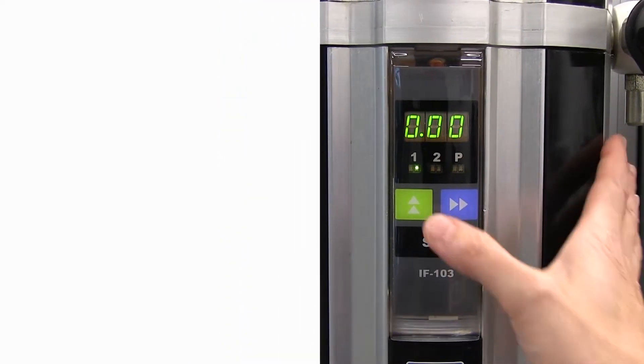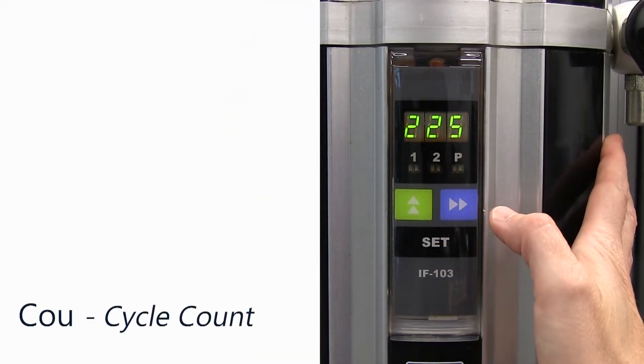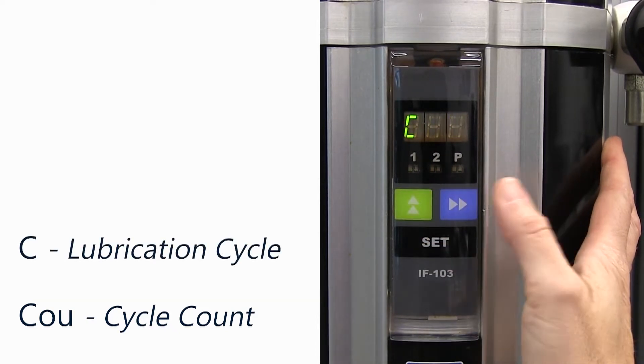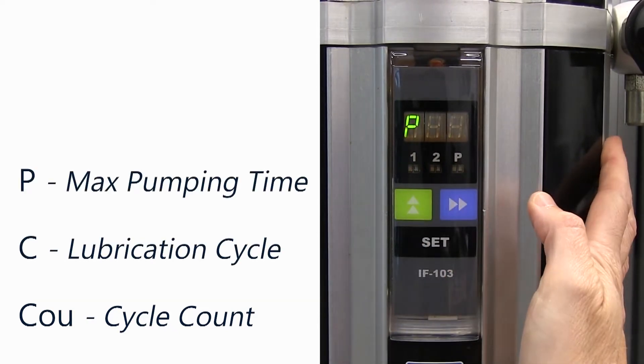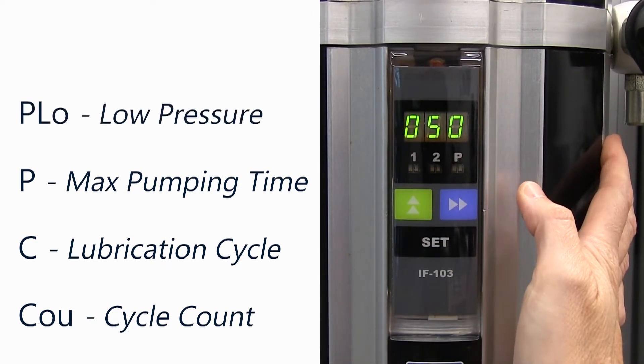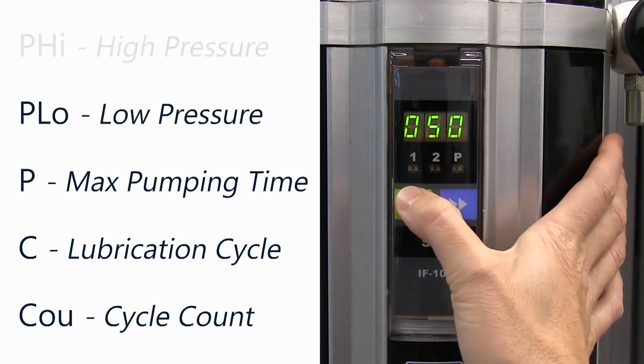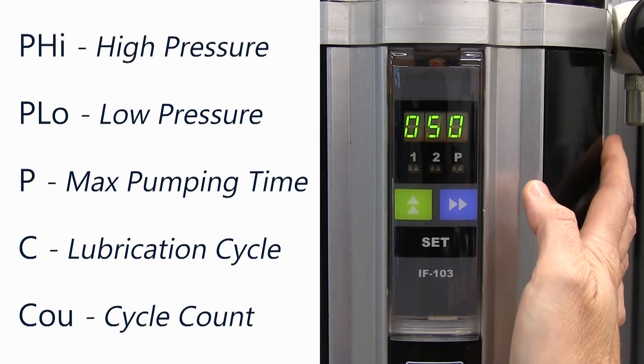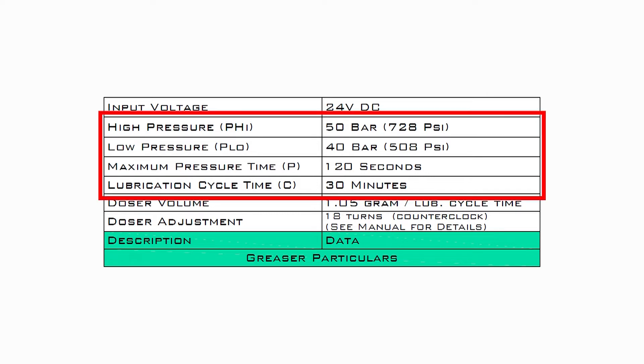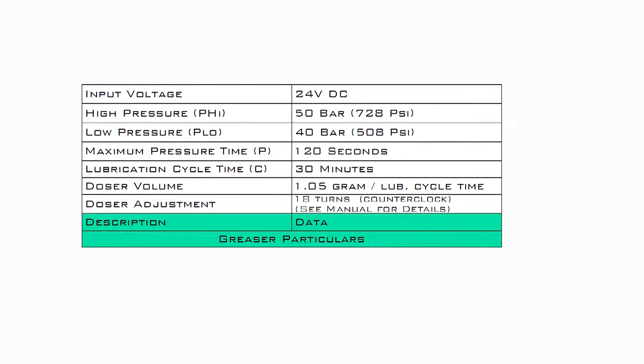Next, press the green up button to navigate through the standard parameters: lubrication cycle (C), maximum pumping time (P), low pressure set point (PLO), and high pressure set point (PHI). Check the values shown on the display against the values in the automatic greaser central piping arrangement drawing.